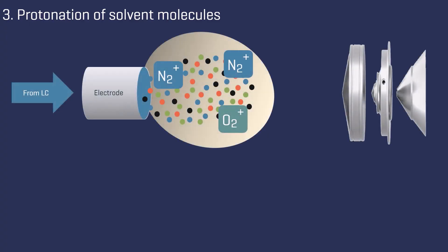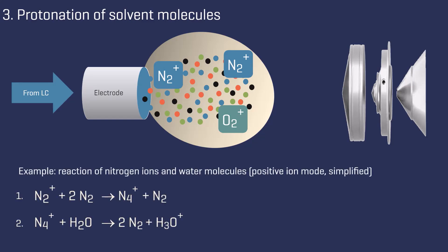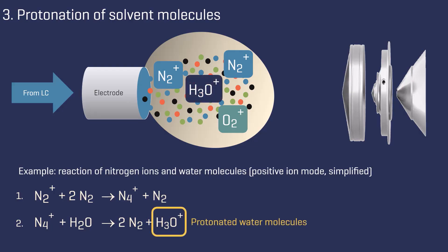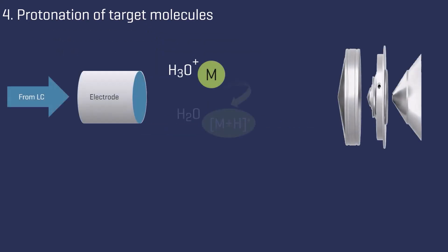The ionized gas molecules initiate a series of reactions with other gas and solvent molecules. To illustrate this process, we will use nitrogen ions interacting with water molecules in the positive ion mode as an example. The important outcome of this reaction cascade is the formation of protonated water molecules. In the next step, protons are transferred from the solvent to the target molecules.